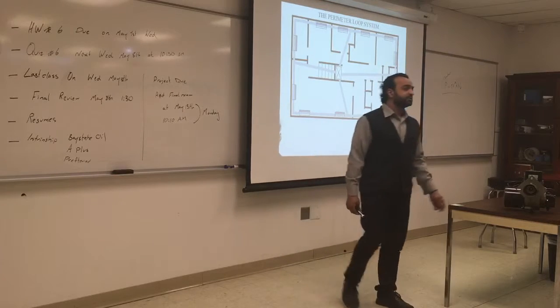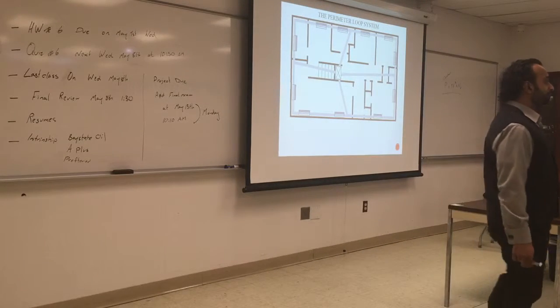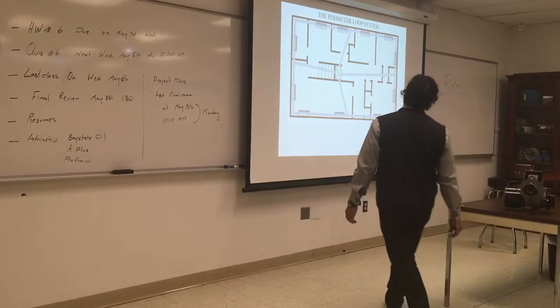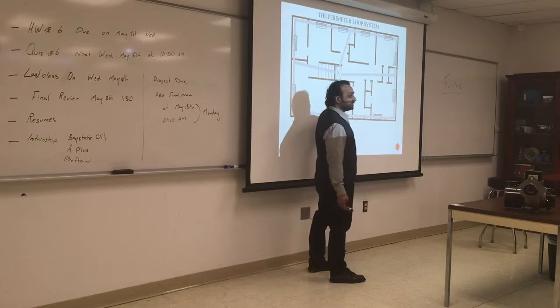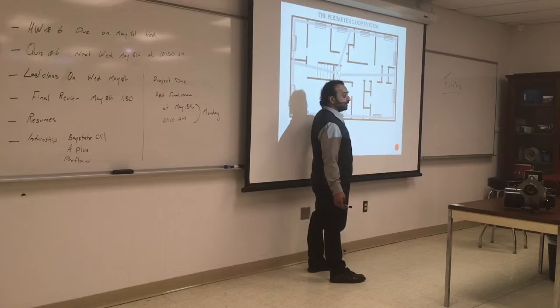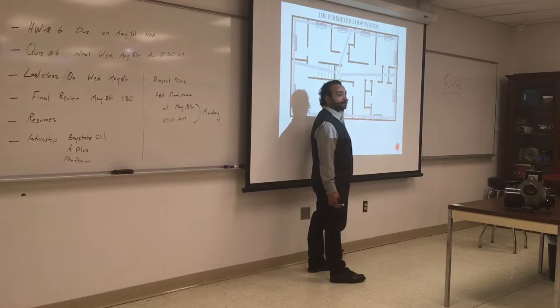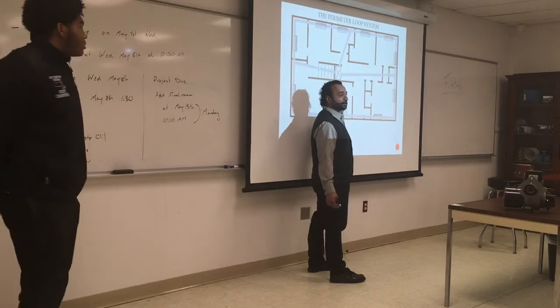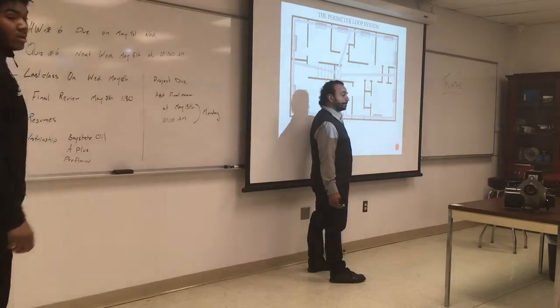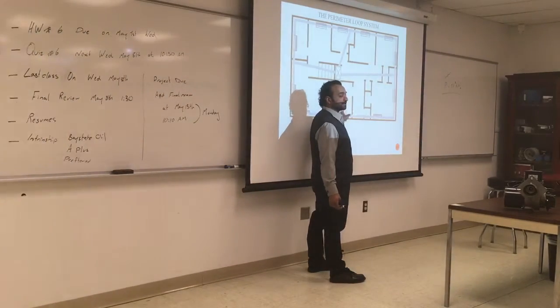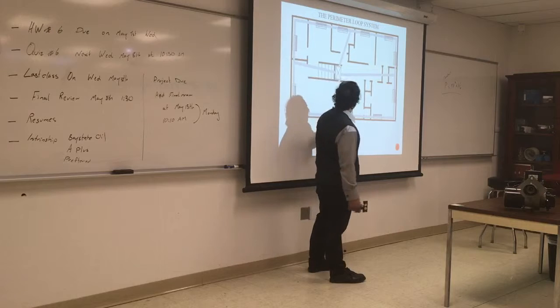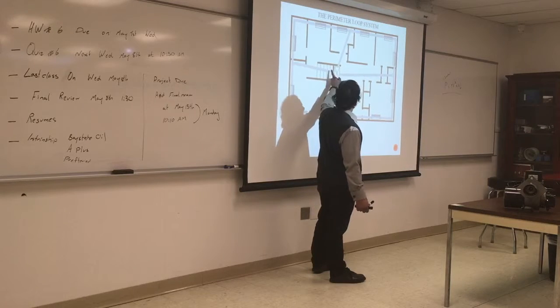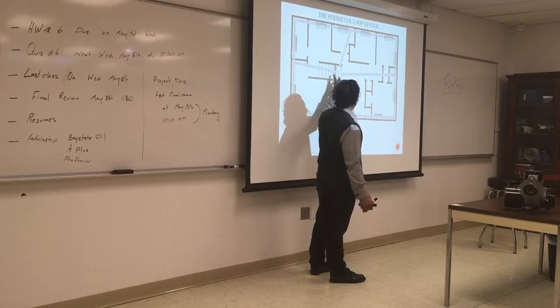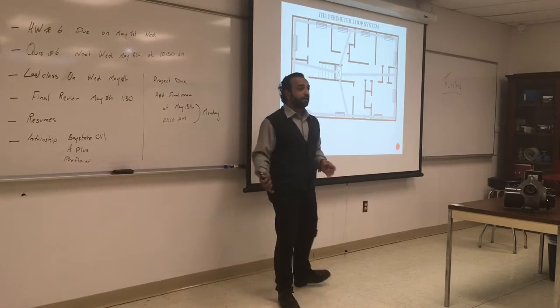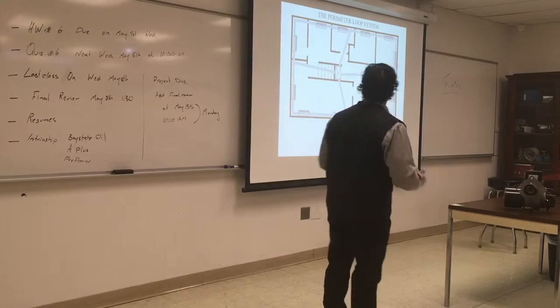Where do you think you should put the dampers? And why? They say it's better to put the dampers as close to the main unit as possible. Why? If you put the damper here, air is still going to push around here, and air is compressible, and that will lead you to have a lot of vibration. So you'll have a lot of noise and a lot of losses coming to this leg for no reason. So if you want to have a damper, you might want to put a damper here, and a damper here, if you want to cut off this section. So put the dampers as close as possible to the unit.